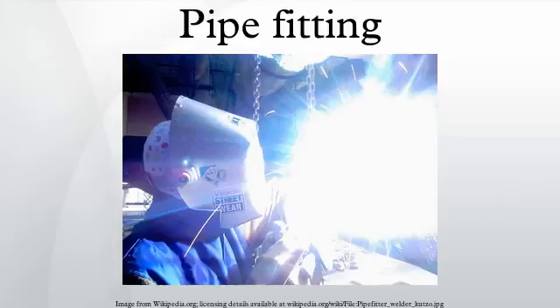Beyond domestic or light commercial settings, steel pipe is often joined by welding, or by use of mechanical couplings made by companies such as Victaulic or Anvil International that hold the pipe joint together via a groove pressed or cut into the ends of the pipes. Other variations of steel pipe include various stainless steel and chrome alloys. In high-pressure situations these are usually joined by TIG welding.